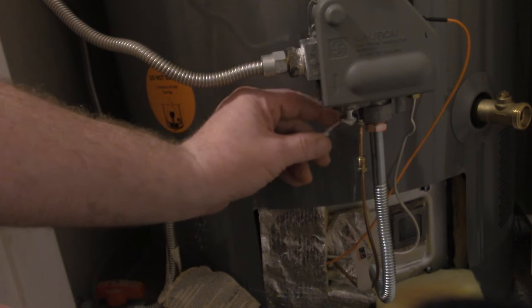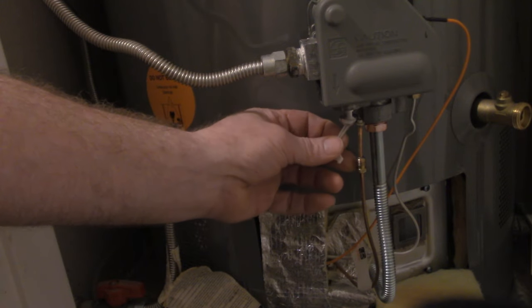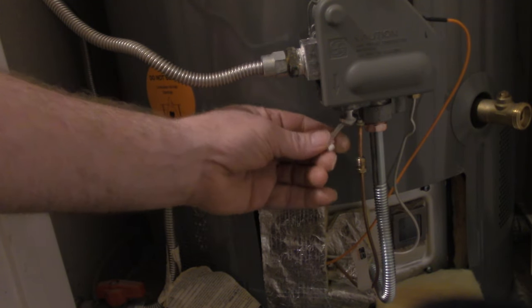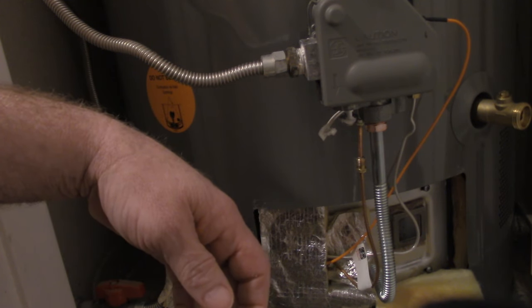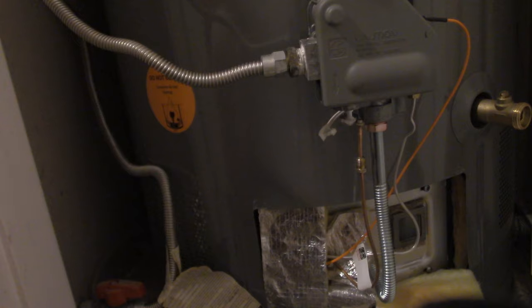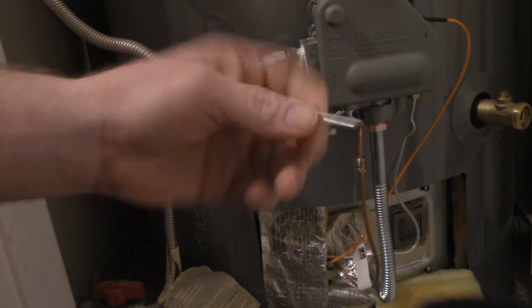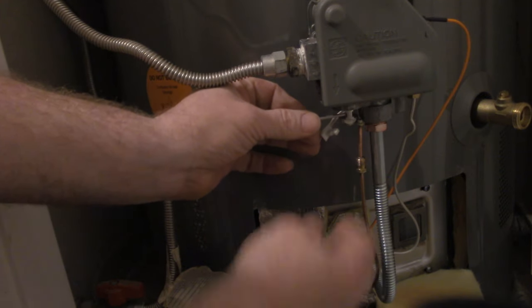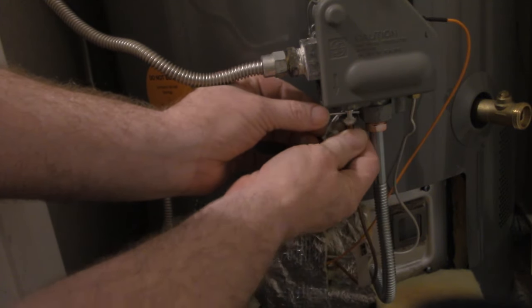So a couple options that you have there to troubleshoot this, you can actually cut these wires and twist them, strip them off and tie them together and put that back in there. Another thing that you can do, and this is what I've done, is you can just find a small nail, this happens to be an aluminum pop rivet, and hold that in there and then reconnect your thermocouple.